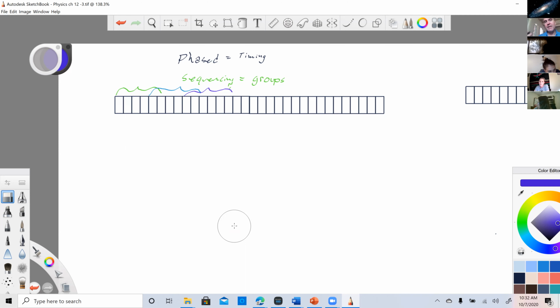By the way, on this type of linear sequenced array, that might be the face of the transducer, but it is not the aperture. Now remember, the aperture is the width of the beam. So here's the aperture for the green beam. This was the aperture, basically from here to here for the light blue, and that purple beam, the aperture was from here to here. Makes sense? The aperture is not the whole face.